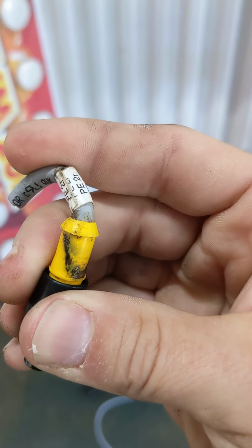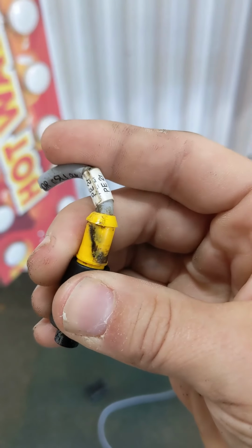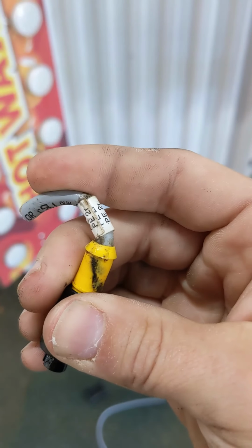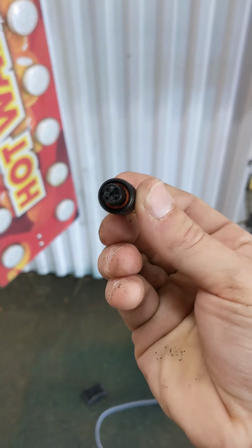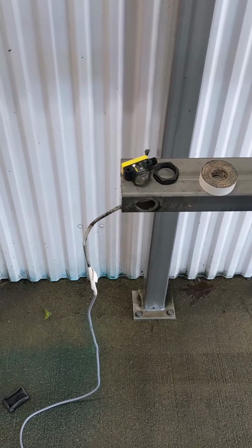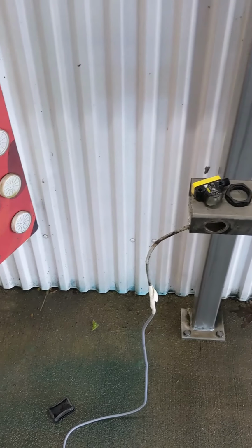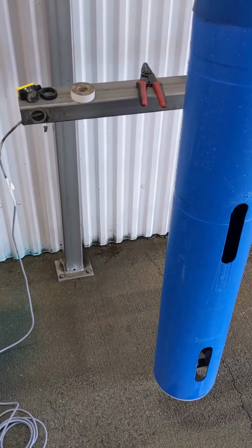Right there. Do we see that? About midway on the 45 part, there's a hole there, and I'm thinking that the water just got in there through that. These are usually what goes bad. The eyes are usually not what goes bad, but again, if you unplug it and you still have a signal, then it is the cable, not the photo eye.